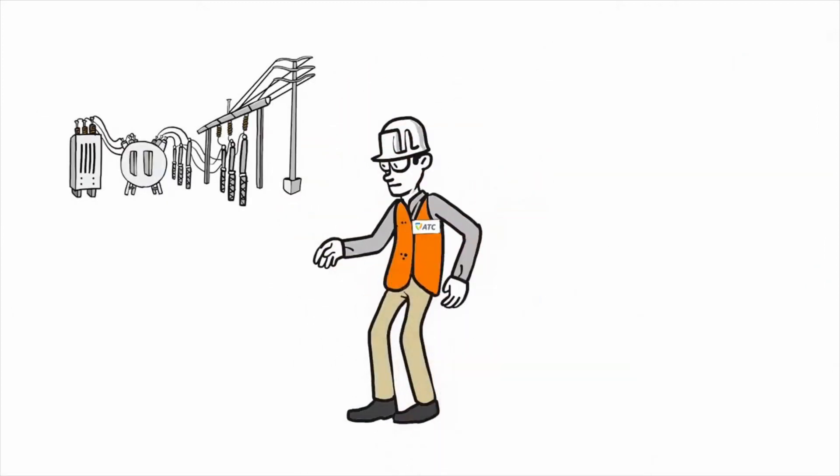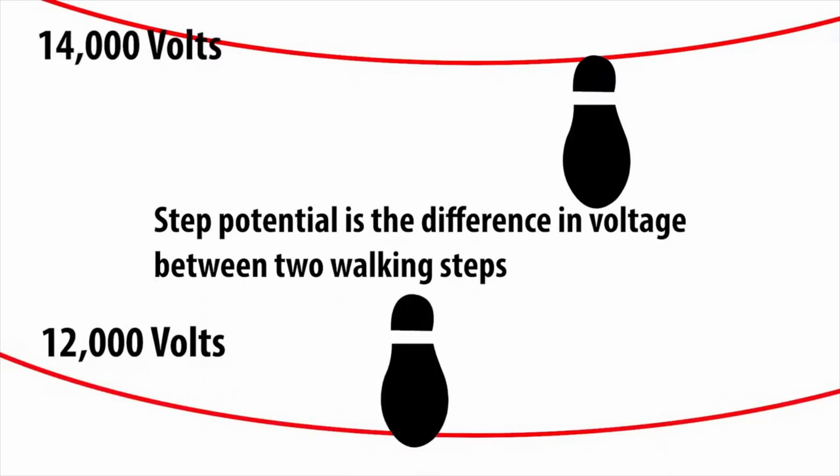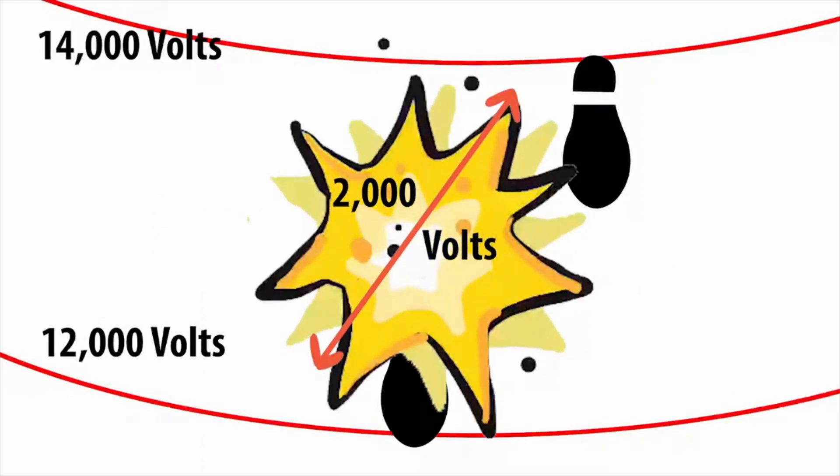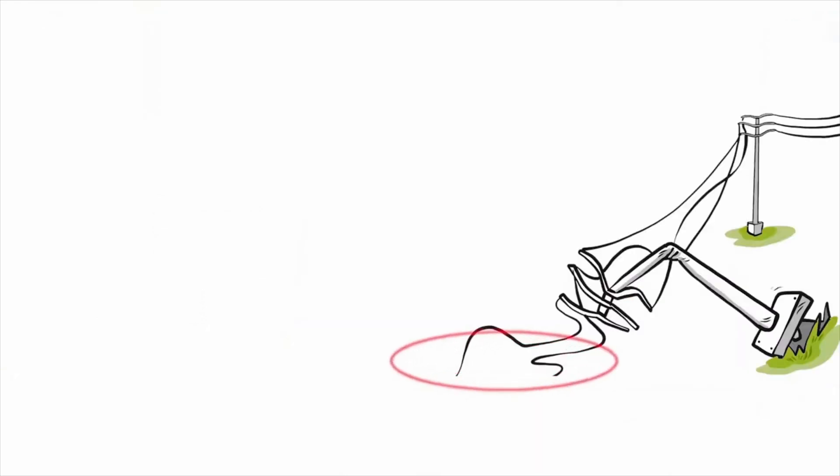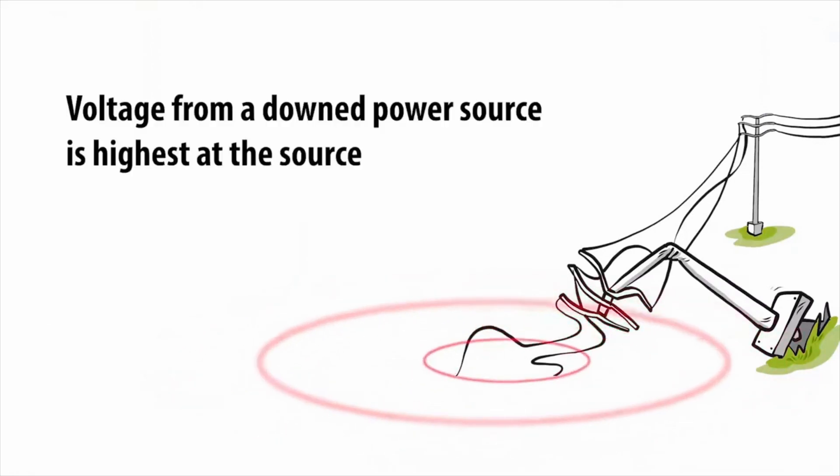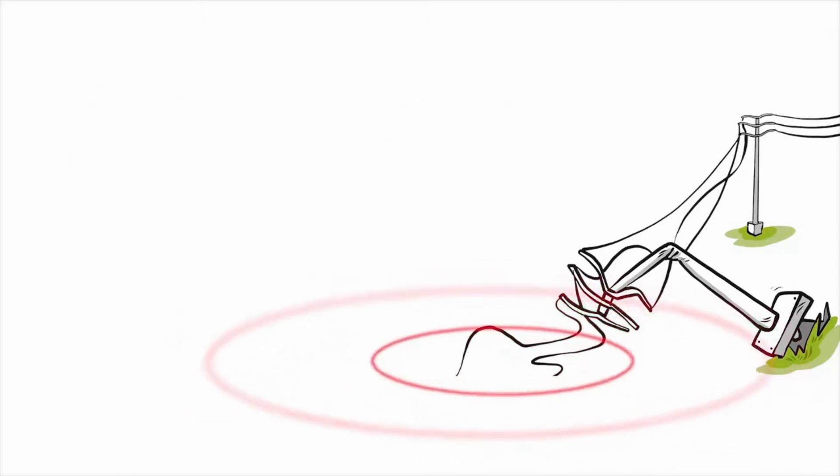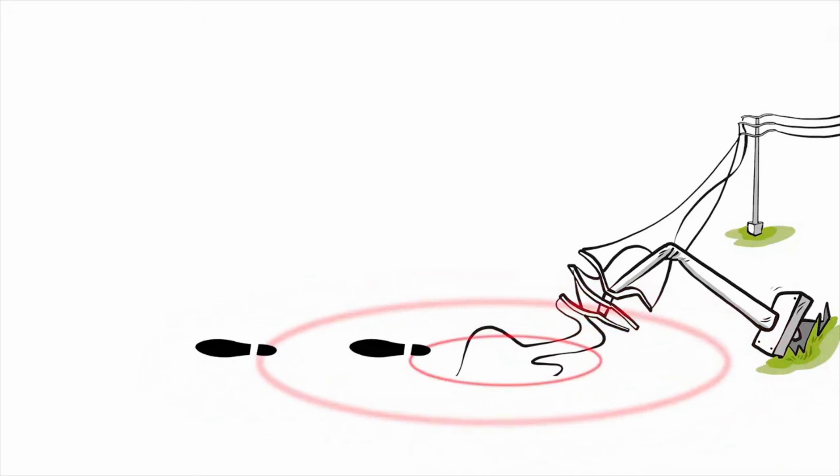It's important to understand step potential when working around electric sources. Step potential is the difference in voltage between two walking steps when the Earth becomes energized from a downed power source. This difference is caused because voltage from a downed power source is highest at the source and fades as it moves outward from the source. Stepping on two different voltages at the same time may electrocute you.